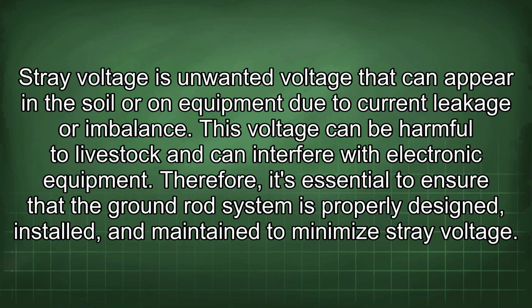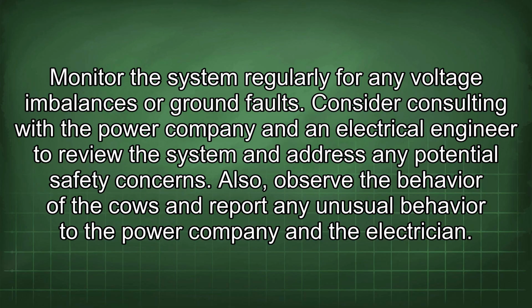Stray voltage is unwanted voltage that can appear in the soil or on equipment due to current leakage or imbalance. This voltage can be harmful to livestock and can interfere with electronic equipment. Therefore, it's essential to ensure that the ground rod system is properly designed, installed, and maintained to minimize stray voltage. Monitor the system regularly for any voltage imbalances or ground faults. Consider consulting with a power company and an electrical engineer to review the system and address any potential safety concerns. Also, observe the behavior of the cows and report any unusual behavior to the power company and the electrician.